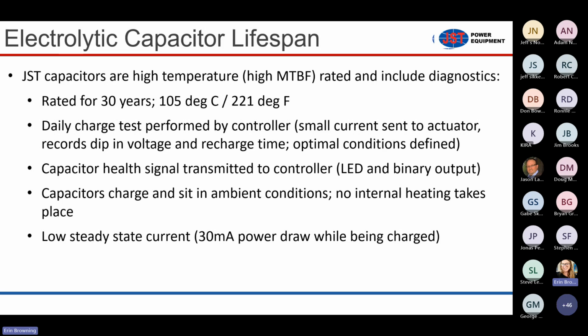We are performing a daily capacitor health check every day. The control board basically sends a small amount of current to the actuator, and then it measures the dip in voltage in the capacitor, and it measures how long it takes to recharge the capacitor. And the microcontroller on the control board has optimal conditions that have been defined. So the controller knows how fast that capacitor is supposed to recharge. And if it's not recharging in the right time frame or it doesn't have the right recharge profile, that's when we get a digital output from the control board saying that there's an issue with the capacitor. So that should be a pretty big peace of mind for the customers in terms of capacitor monitoring.